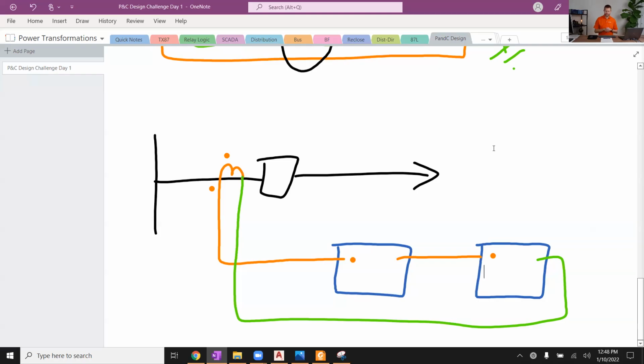I've got a couple more points for CTs, but I do see some questions coming in. Before I get too far behind on them, let me pop back. As you mentioned, taking VT from bushings and or from the line, almost identical. So I guess you're pointing out that whether you use line side PTs or bus side PTs from a protective distance element, for example, it will work either way. There's some pros and cons to that. You know, if the breaker is open, you don't have a true picture of what your line voltages are.